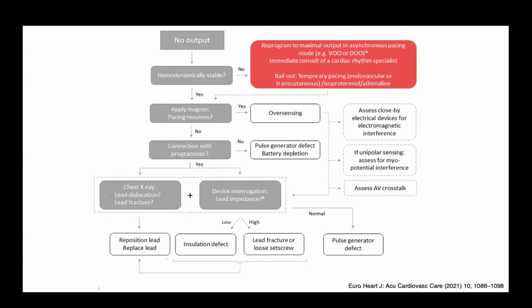If the patient is hemodynamically stable, then applying a magnet can differentiate some of the issues. If the pacing comes back with applying the magnet, then there may be an oversensing issue. First of all, we have to check if there are any nearby electrical devices with an electromagnetic field that could have interfered with the device function, or if the sensing is programmed as unipolar, especially in some of the old leads. We have to assess for potential interference with chest wall movements, or if there was any AV crosstalk.